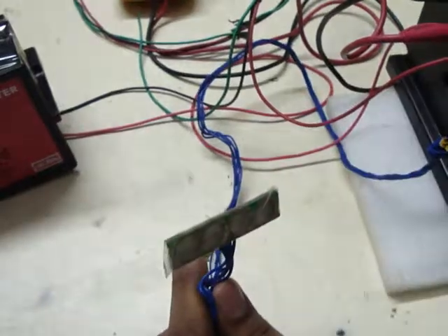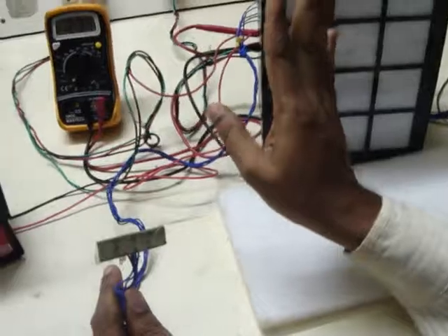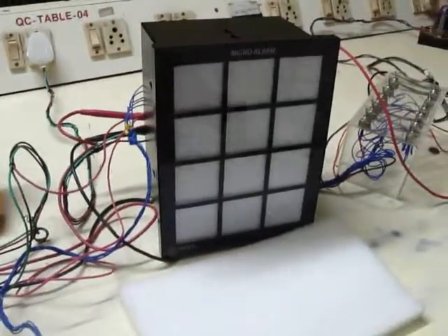We have made a temporary arrangement with the keypad. When you press test, all the windows will start to flash. When you press acknowledge, the hooter will turn off and all the windows will become steady. Then reset. This is to test the healthy condition of the annunciator.